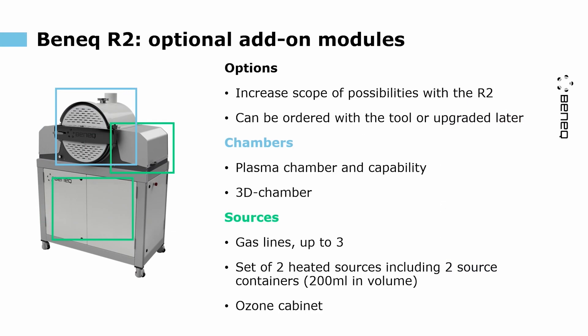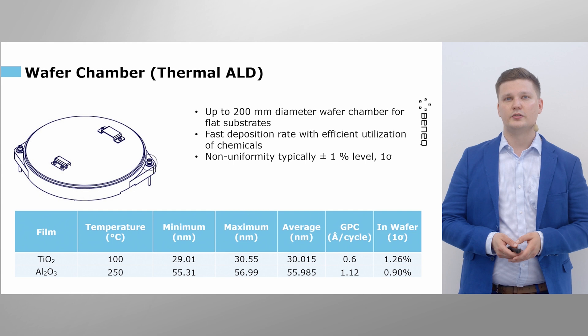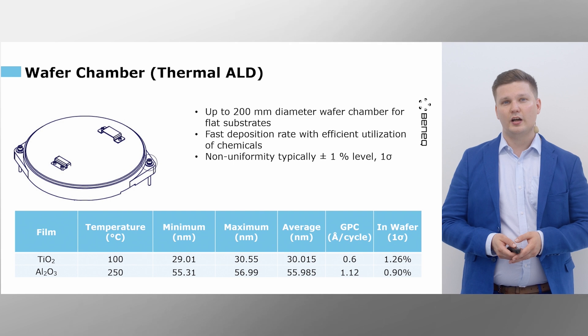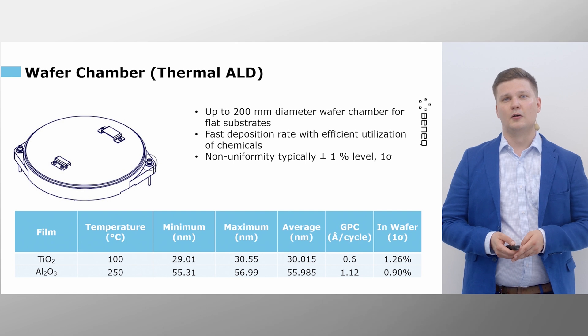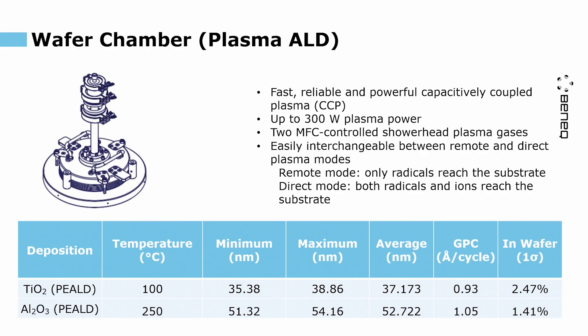There are multiple options you can add to the R2. For example, you could add a 3D chamber and then a set of heated sources. The standard wafer chamber for thermal processing is for up to 200 millimeter substrates. The uniformity levels are high, typically for standard oxides at a level of 1%.